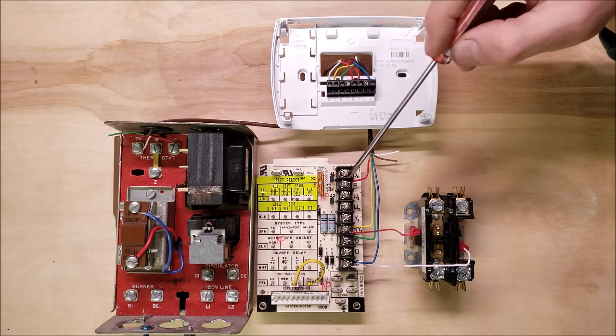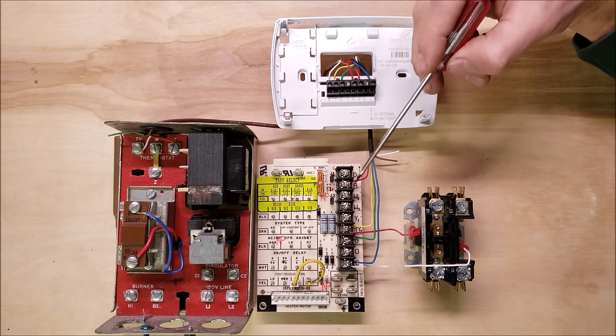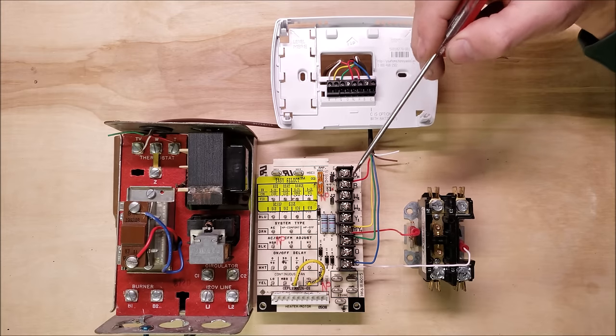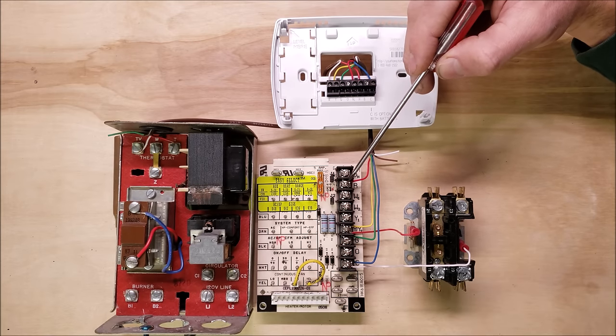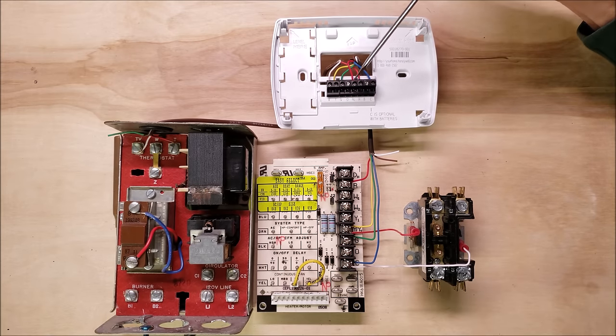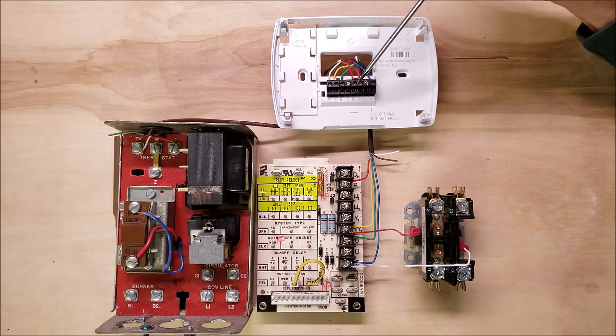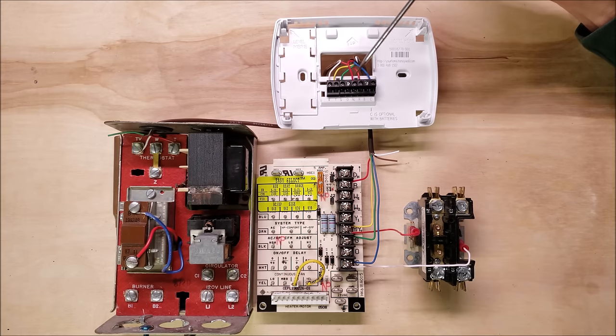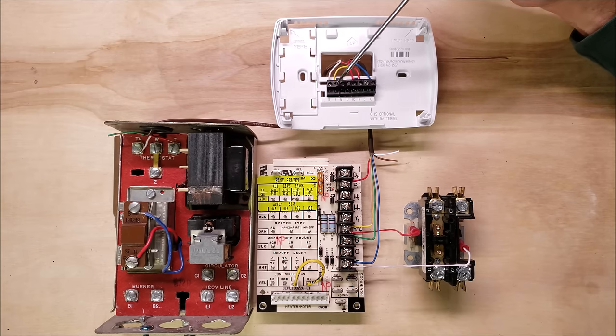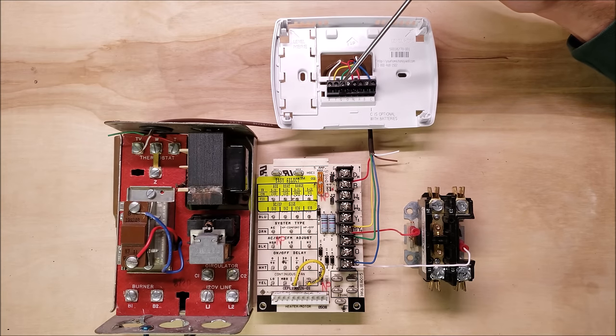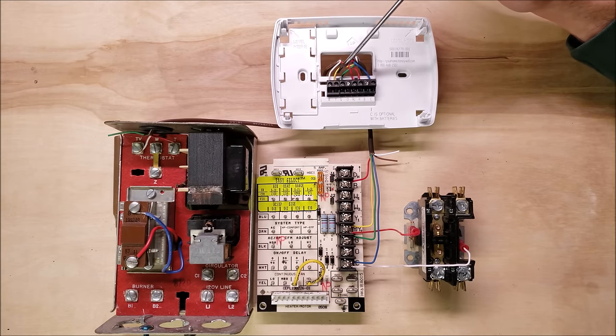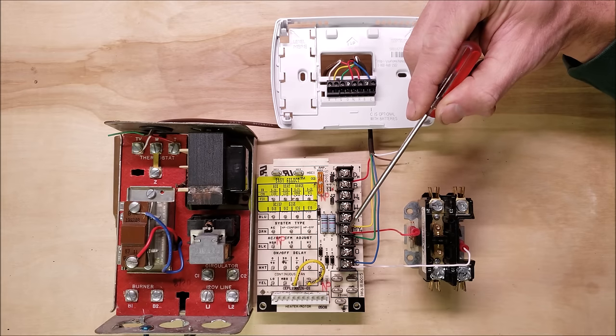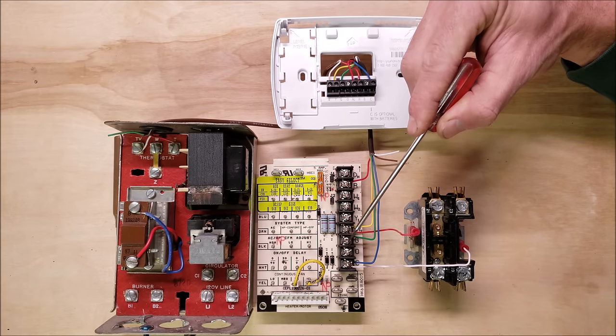In reference to your air conditioning unit, your R right here is your 24 volt power from your indoor air handler heading to the thermostat over to RC. When you're calling for cooling, RC connects to G and Y and that sends a 24 volt signal back in this green wire and yellow wire over to Y, Y2 and G.